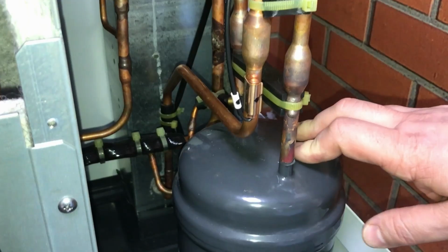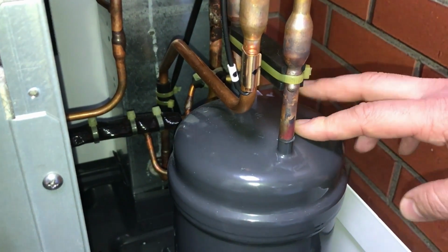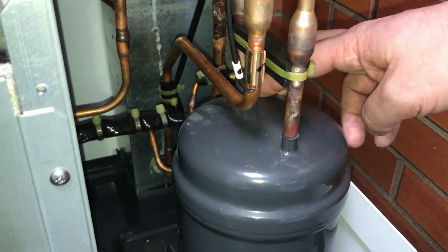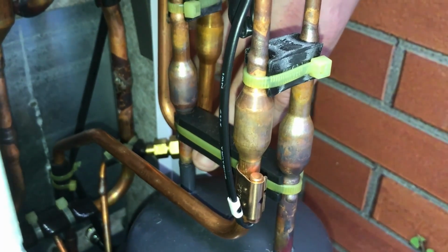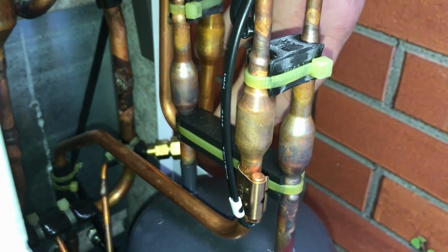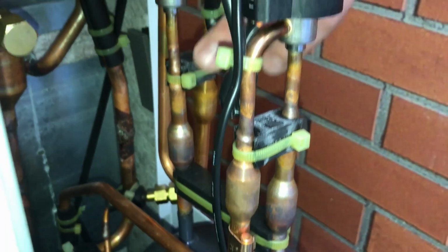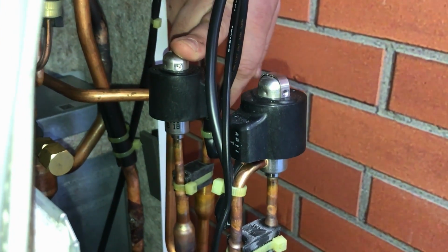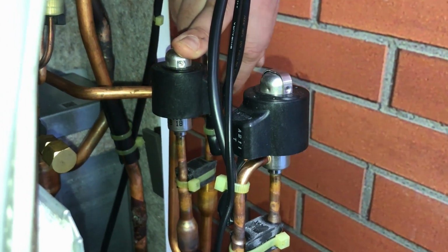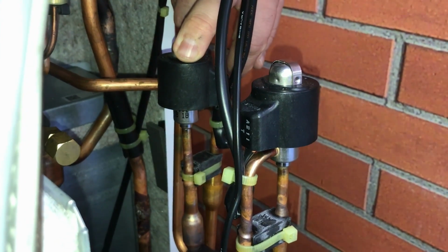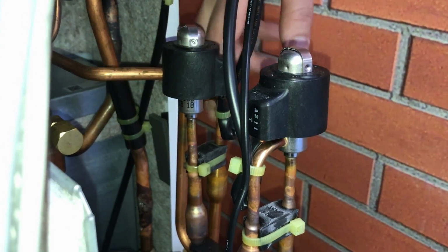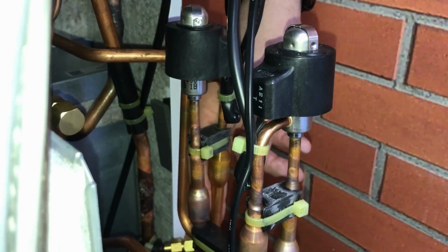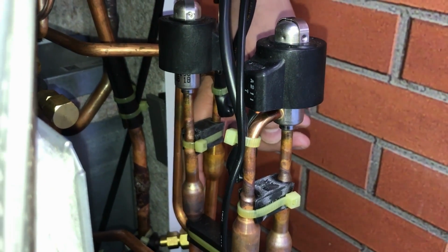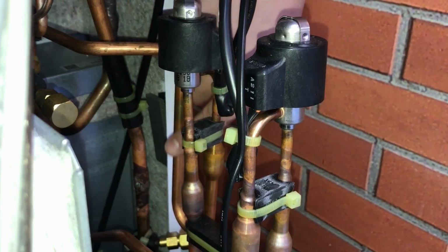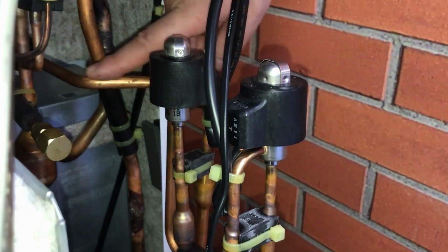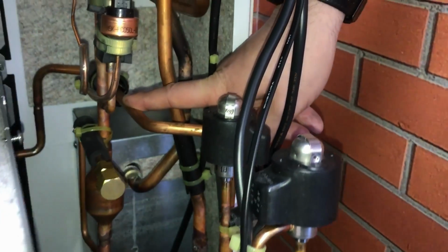So a nice pool of liquid refrigerant inside of here, and then we're going to draw off that liquid refrigerant from the back of there. So now drawing off liquid refrigerant from that liquid receiver, past this valve here, and this is actually doing the expansion work. So this is actually taking that refrigerant from being a high pressure to being a low pressure. So you'll feel on the other side there significant temperature difference between that side and that side. That refrigerant passing from there back and towards the coil.